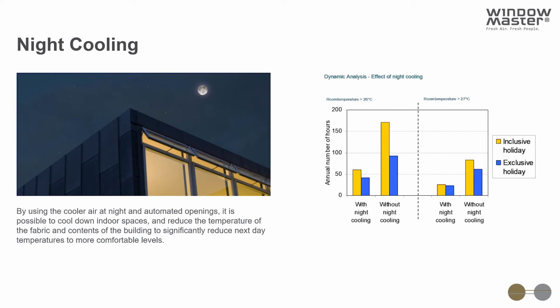On the right hand side here, you can see an example of a typical room that we've modeled, and the yellow bars show inclusive of summertime holiday, so that's typically for a commercial application that runs all year round, and the blue bars show a typical education development whereby they are closed during the summer months. You can see that with night cooling we can reduce the number of hours at higher temperatures over 26 degrees by half by implementing an effective night cooling strategy. That's a significant impact on comfort, and it can also help to reduce the peak temperatures in the room by around 10 degrees as well, depending on the building construction. Night cooling is a really important part of any effective natural ventilation design for modern buildings.